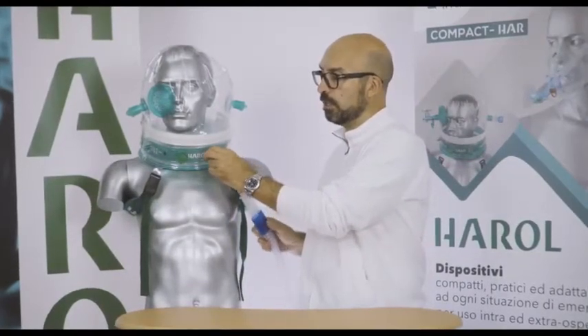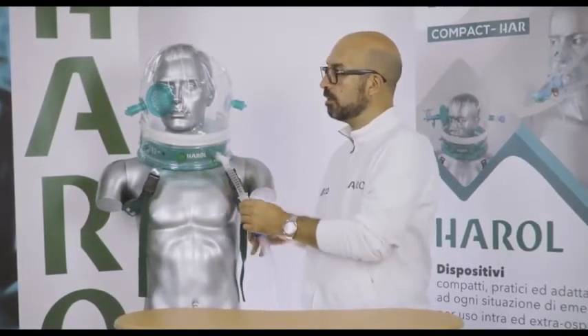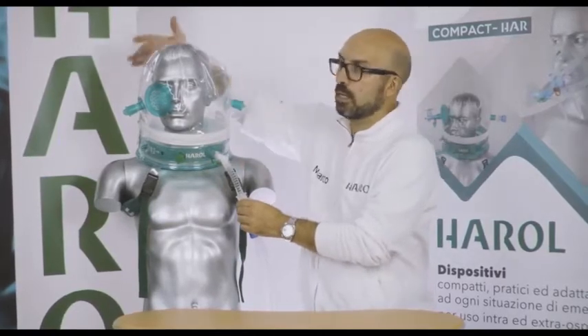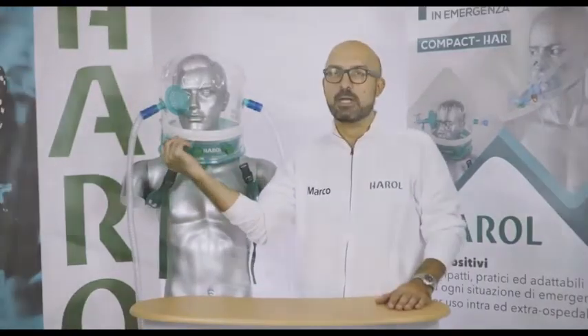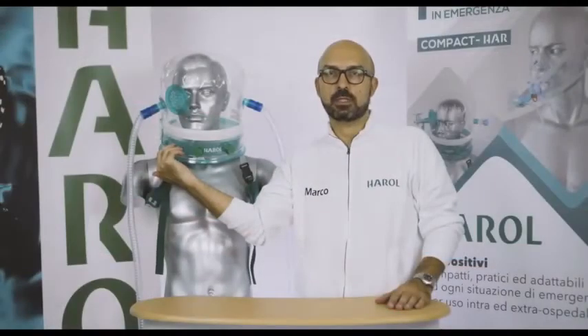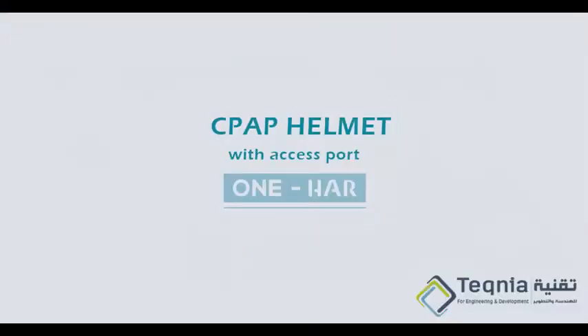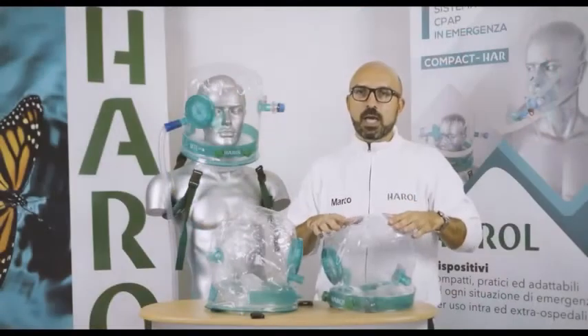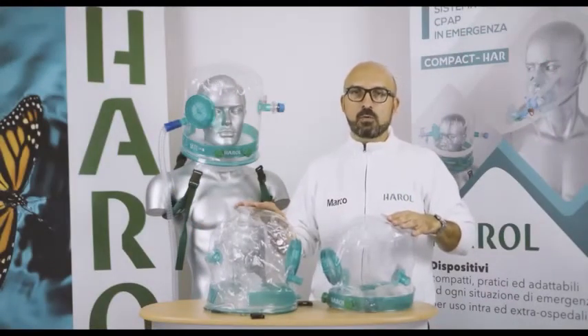It's sufficient to put the two provided caps on the side connectors and connect the catheter mount on the frontal access port. On the side of the band, you will find an access port for measuring PAP with a manometer or an external monitor to check the pressure. In the configuration for the CPAP therapy, the volume is around 15 liters to guarantee a good CPAP therapy. The device weight is about 400 grams.